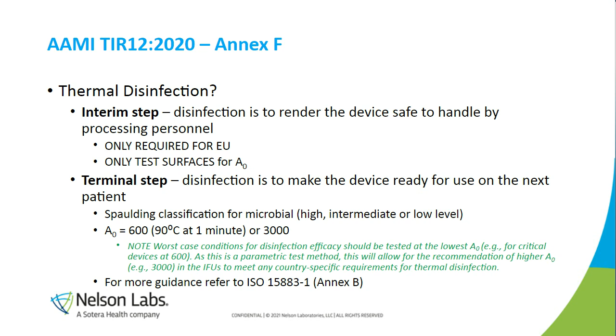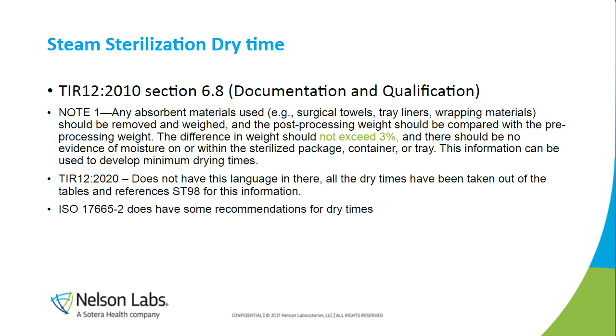Notable updates to the steam sterilization section were the removal of the dry times acceptance criteria. For additional information on dry times, the readers are referenced to the new ST98 and the ISO document 17665-2. And then finally, a full cycle approach was added to give sponsors additional flexibility in how steam sterilization validations are performed. And for my fellow math and data nerds out there, we've included some beautiful math showing that the sterility assurance level achieved using both approaches is the same.